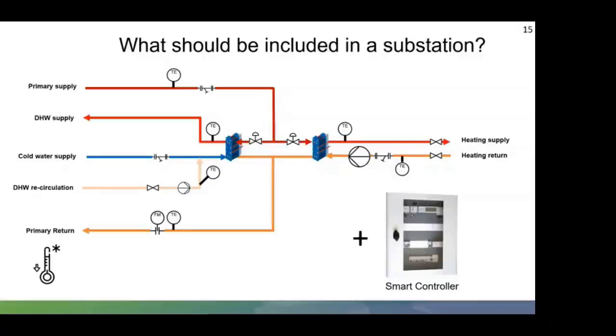So what should be included in a substation? When we are designing a substation, it is important to consider all the components that are used carefully to minimize the overuse of valves and unnecessary components. Correct size heat exchangers, control valves and pumps and the combined design selection are very important to the efficiency and control of a substation, along with the temperature and flow sensors. When this is all connected through an intelligent controller, you will achieve the ability to monitor how the substation is working, to enable you to make adjustments to its flow through the control valves and pumps, which in turn makes the system more efficient and saves the amount of energy being used whilst not impacting on the end user. So again, above is a simple substation, linked with a smart controller, 2 plate heat exchangers, a couple of temperature sensors and valves, providing heating and hot water into a typical building.